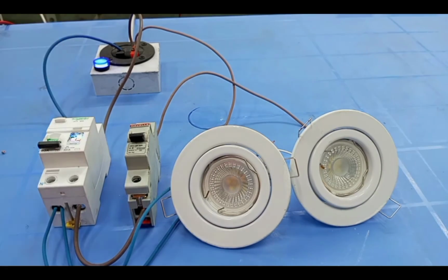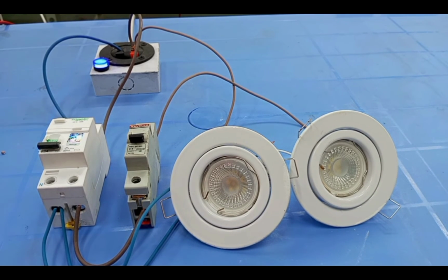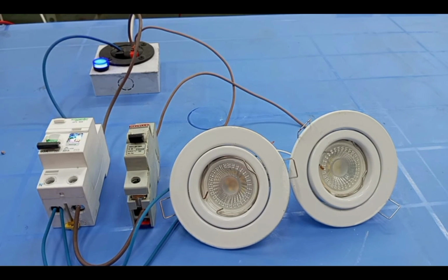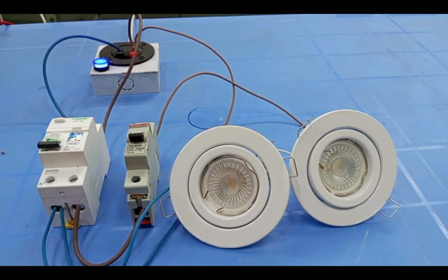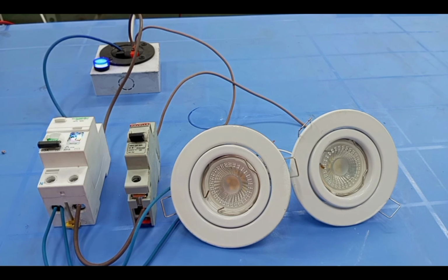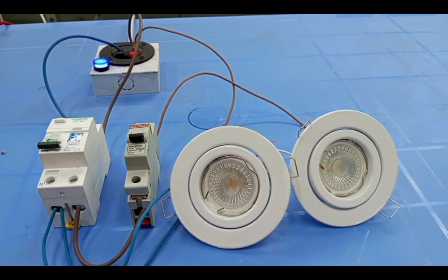And so that becomes an imbalance between the live and then the neutral. And it is the same thing that happens when there is an earth fault in the wiring. An earth fault means that somehow part of the current that is supposed to be flowing only through the live conductor is now flowing through a metal part of the wiring. And so when you have contact with that electrified metal part, the current that is supposed to flow through your body to give you electric shock creates that imbalance between the live and the neutral to break the circuit.